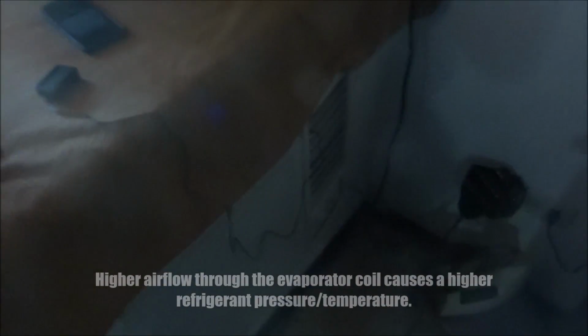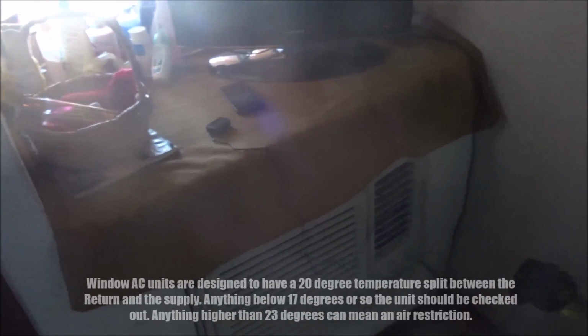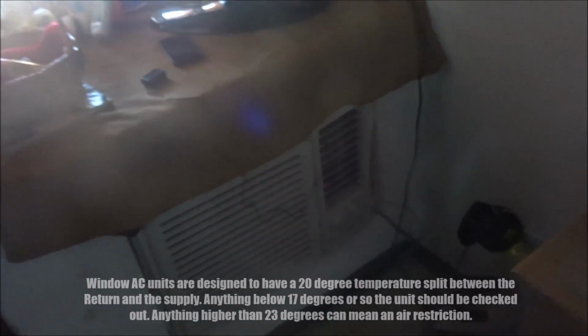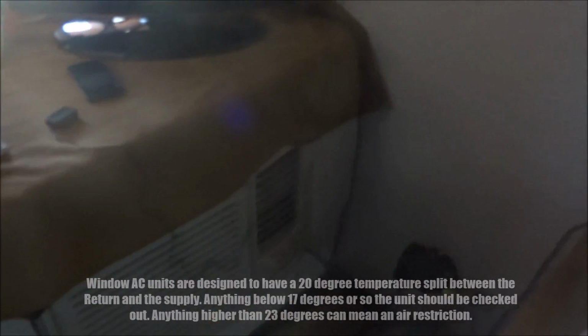This thing is cooling. Now most window AC units, or at least the modern ones, are designed to have a temperature split such as the Delta T split on the central AC units, but on the window units they're designed specifically for a 20-degree difference Fahrenheit, which actually translates to 11 degrees Celsius temperature difference between the return and the supply. So currently on high cool, you can see the temperature went up a little bit.